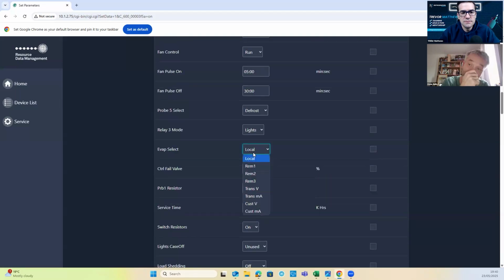So local is saying, right, I'm using probe 3, my evaporator probe, and that's how I'm going to sense my evaporating temperature. I can tell it to read a probe from the network, from a hub that I'm connected to, or from a network device using REM 1, REM 2, and REM 3. I can plug a transducer into it. Usually, by default, we're using trans mA if we do that. Transducer, milliamps, right? And then it's going to be looking for you to set the settings down at the bottom to tell it the range for the transducer, which we'll come to in a moment.